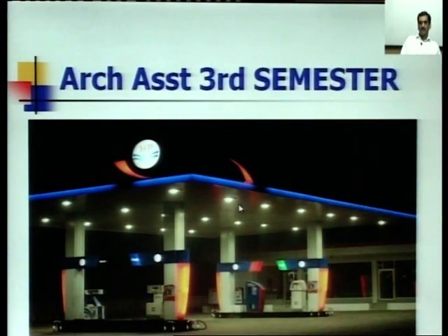A standard canopy is around 250 to 300 square meters, so we are going to have around 24 to 30 lights in the canopy. If we connect these lights in series, we can connect 2 or 3 together. We will have another 15 cables for these lights, and 24 cables for these machines.